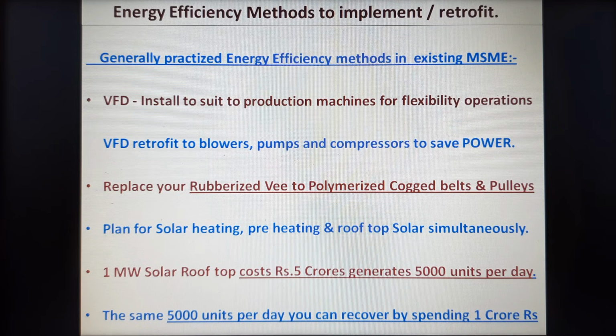Also, wherever you find belt operated machines, either in your production or in your utilities, let us try to replace these rubberized V-belts with polymerized cogged belts and pulleys, and definitely this gives a straightaway savings of 10% on the existing energy consumption of the machine, either in production or utility. Also, you can plan for solar heating or solar preheating. Let us try to make use of the ambient temperature, wet bulb and dry bulb, as well as go for solar rooftop also.